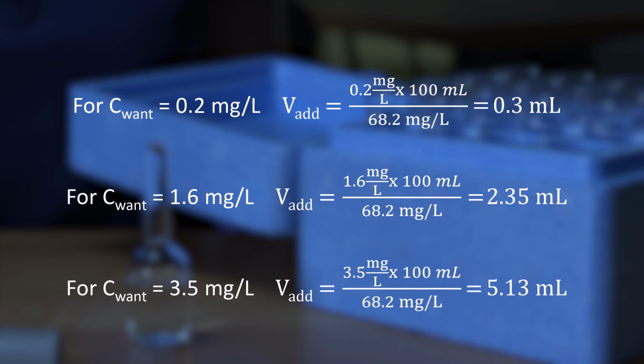For our instrument, when we were to perform this procedure, we would make 3 chlorine dilution standards using the 3 concentrations of C-want, having 0.20, 1.60, and 3.50 milligrams per liter, because they match the concentrations of the factory calibration as performed by the manufacturer. Using the chlorine dilution standard procedure discussed previously, the concentrations to be added to the flask would be 0.30 milliliters for a concentration of 0.2 milligrams per liter, 2.35 milliliters for a concentration of 1.6 milligrams per liter, 5.1 milliliters for a concentration of 3.5 milligrams per liter.